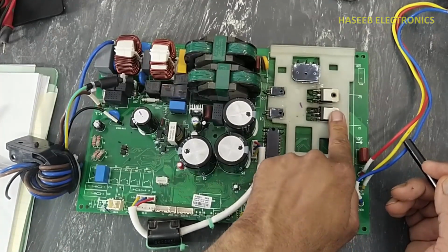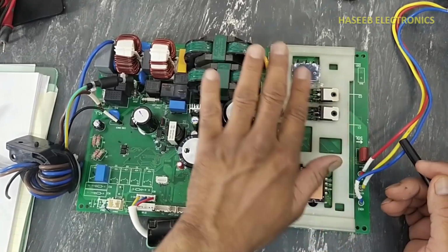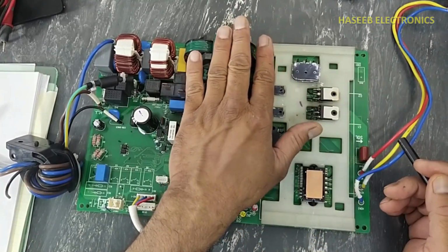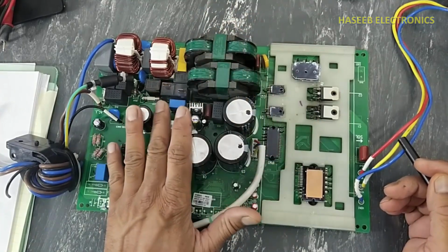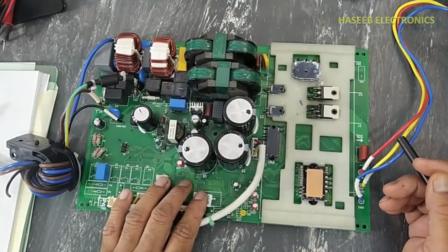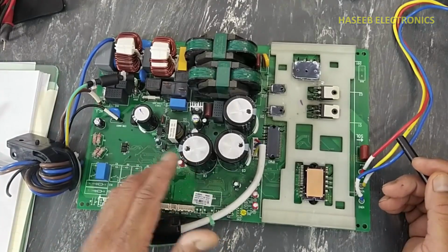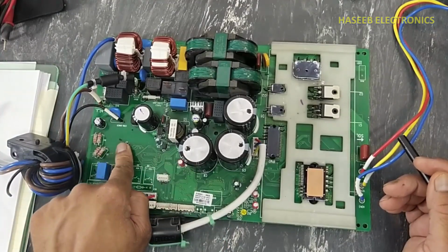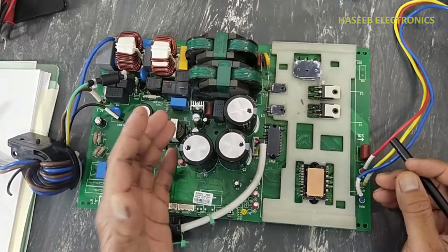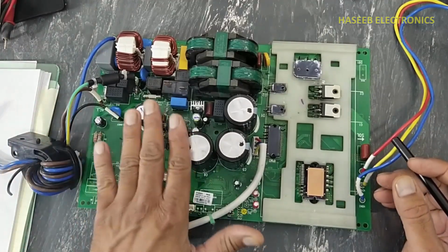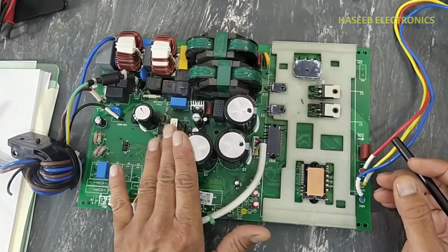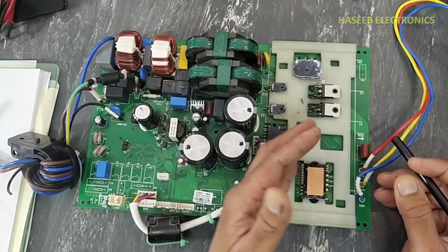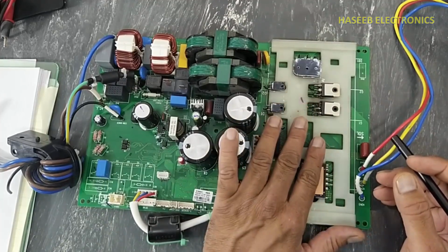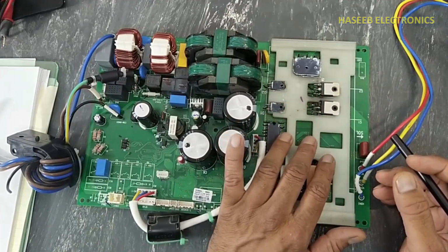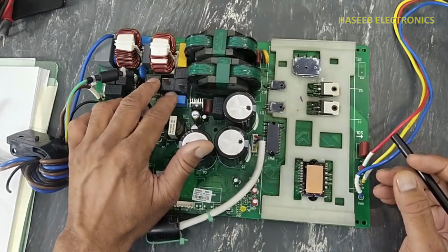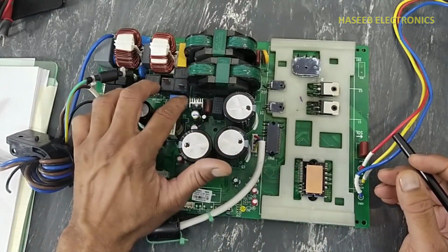When it is short circuit, it will not allow this board to turn on. When it will not turn on, its circuit will not be active, its microprocessor will not be active. As a result, it will also cause failure to communicate. For good communication with the indoor unit, the board must be powered on properly and there is no overcurrent condition or anything wrong. If anything is wrong, especially an overcurrent condition, at that time it will turn off its startup circuit.